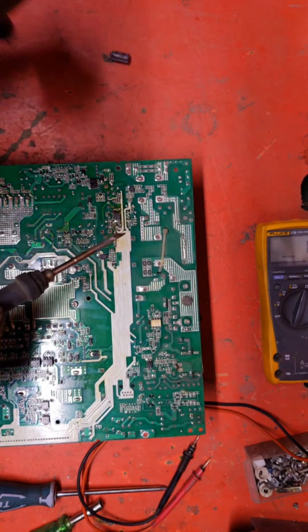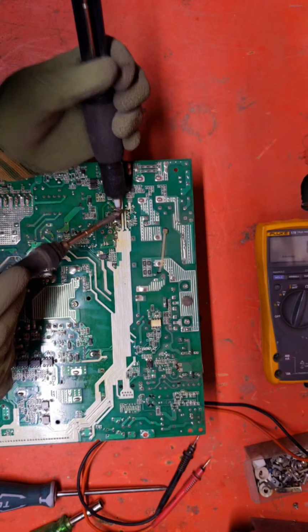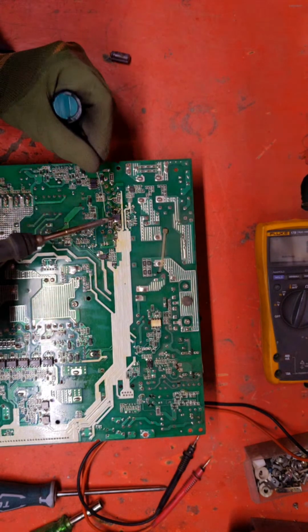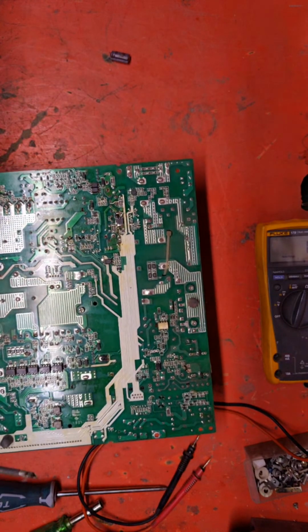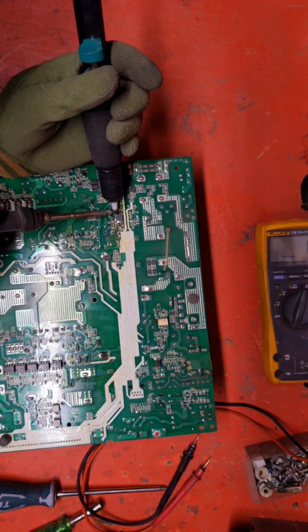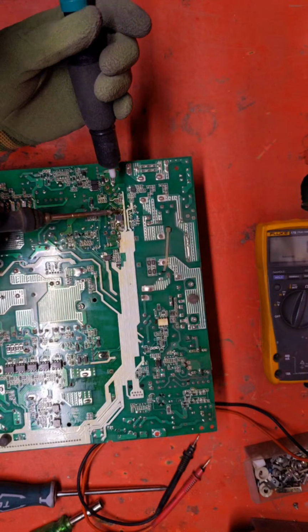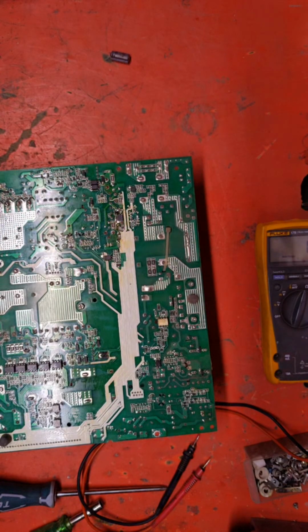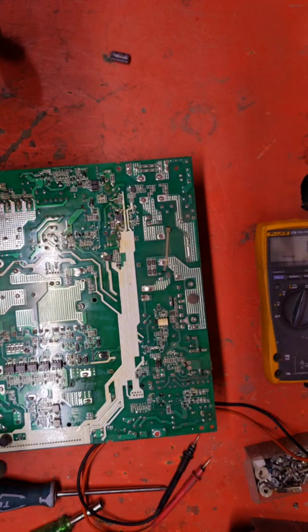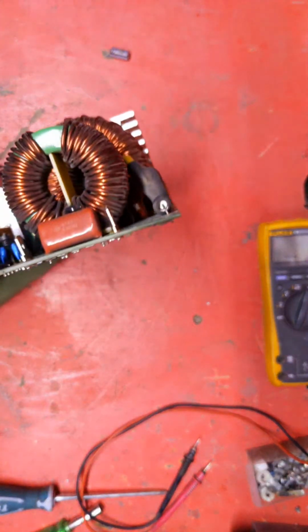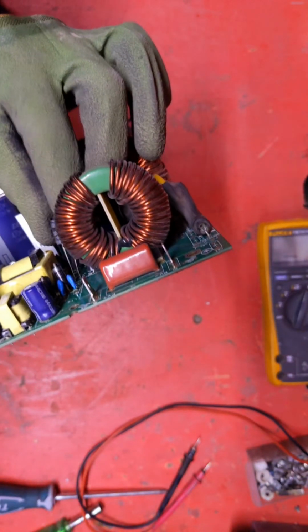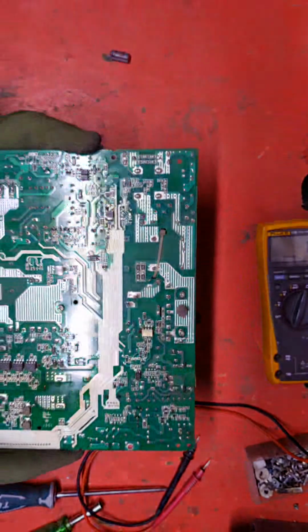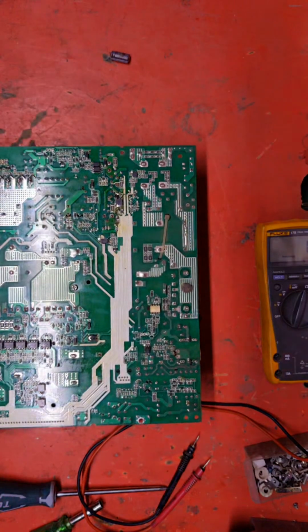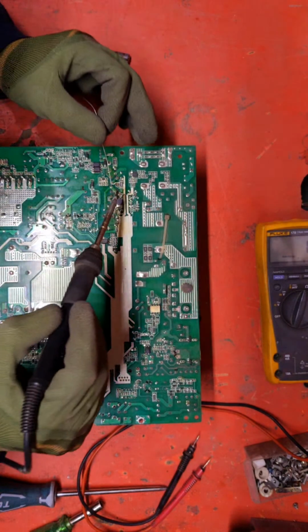But the difficult thing is that we have no LCD, and if I can't repair this, we need to order the LCD or wait for another LCD to check the fault. What fault is the MCU microcontroller detecting? Because everything is fine, the IGBT is fine, the bus start voltage is okay, then why? This is the difficult thing. That's okay. And this is the VM3 latest model.